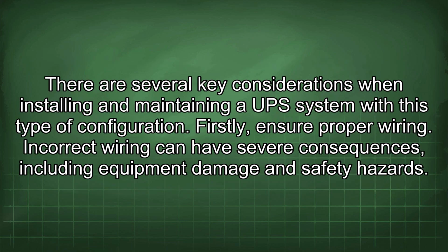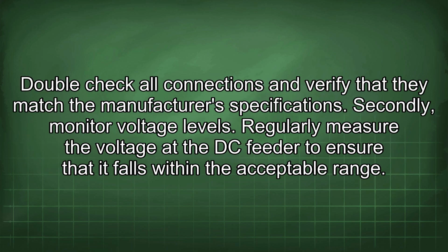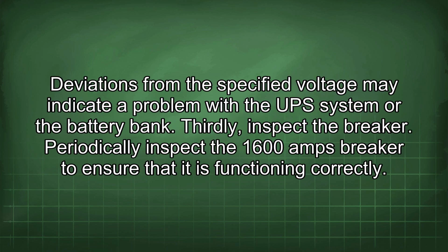There are several key considerations when installing and maintaining a UPS system with this type of configuration. Firstly, ensure proper wiring. Incorrect wiring can have severe consequences, including equipment damage and safety hazards. Double-check all connections and verify that they match the manufacturer's specifications. Secondly, monitor voltage levels. Regularly measure the voltage at the DC feeder to ensure that it falls within the acceptable range. Deviations from the specified voltage may indicate a problem with the UPS system or the battery bank.